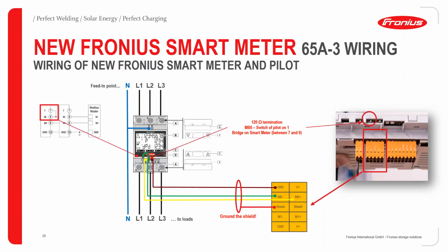Please do not get confused by that, you can choose whatever you like, both are the same. For example, you can go from the smart meter to the inverter via Modbus 0, and then from the inverter to the battery via Modbus 1. That's possible, but you can also combine it like the Symo Hybrid at one Modbus port, so both are possible, depending on what you prefer and what you want to install.